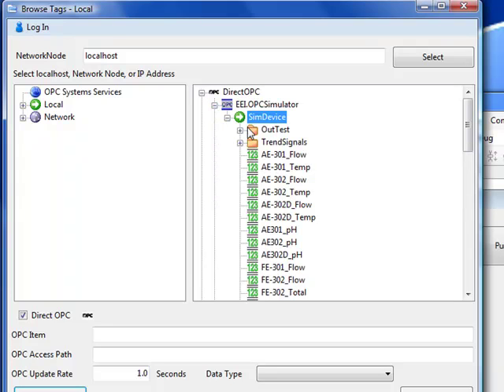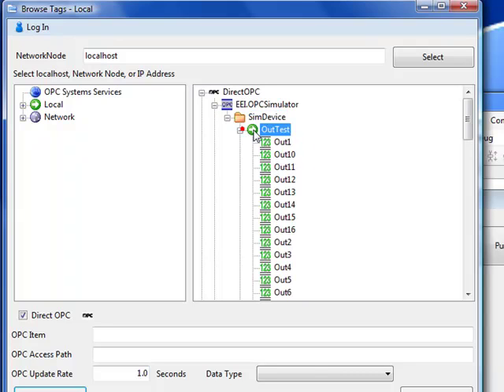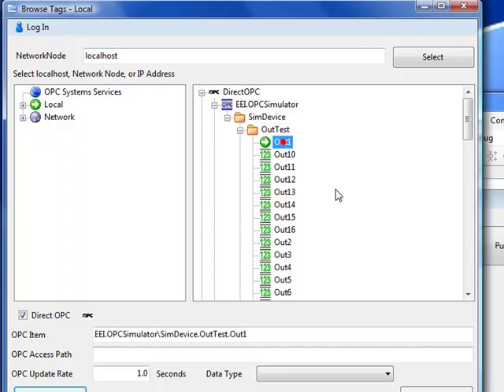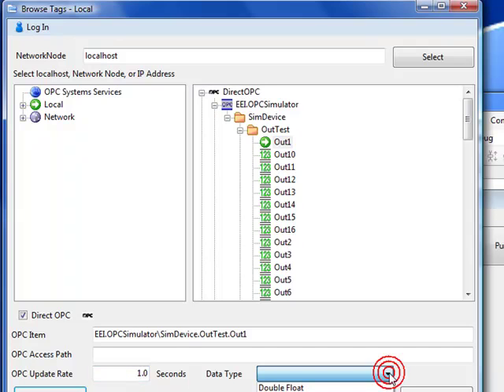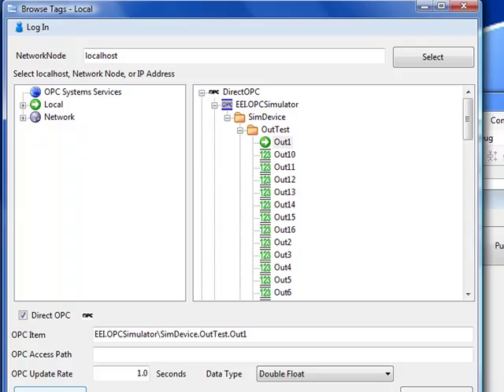which should install with your OPC systems.net software. And if we select under SIM device, there's an out test group. Go ahead and expand that out test group and we have the signal out one. We're going to define an OPC update rate of one second and a data type we're going to use as a double float. We'll click OK.